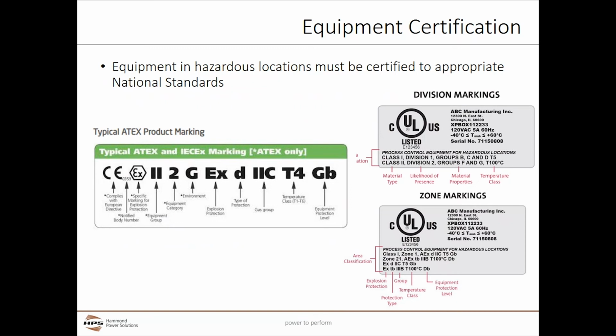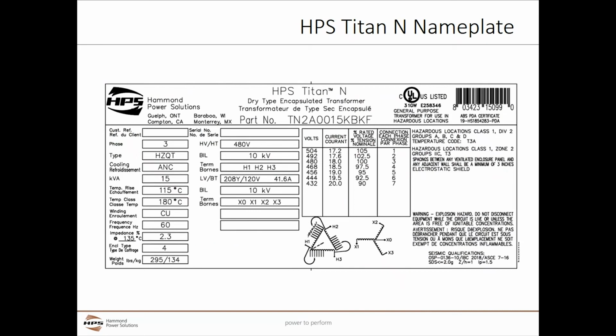ATEX and IECEx equipment is classified by group, type of protection, gas and dust group, temperature class, and equipment protection level. And I mentioned already that there are some differences between Titan N and Titan X in regards to nameplates. So this is a sample of how our Titan N nameplate looks. Some of the fields are required by UL, and some of the fields we just add as further clarification to the customer, or how to actually do the wiring.